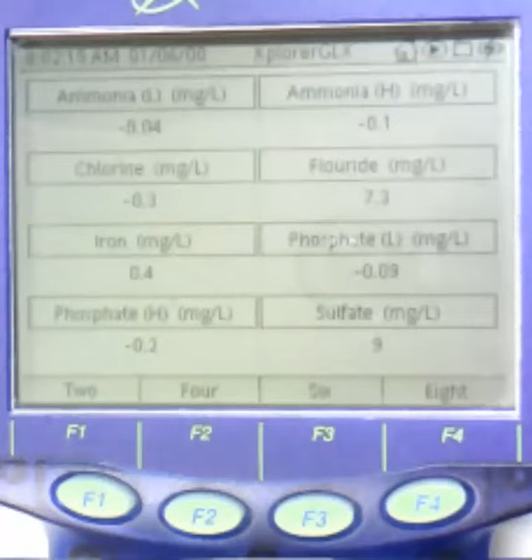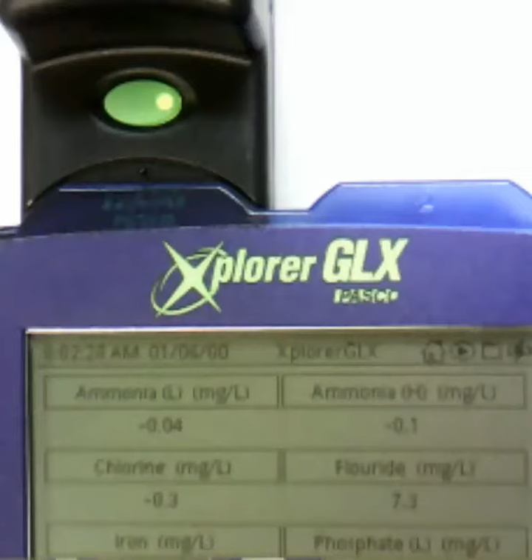So now I'm going to calibrate my colorimeter. I'm going to do that by removing the calibration ampule from its protective case, and I'm going to place it into the sensing chamber for the water quality colorimeter. Next, I'm going to place the light cover on top of it, so the only light passing through the sample is what is produced by the colorimeter. Next, I'm going to press the calibration button, and I'm going to wait for the green light to turn out to let me know that the device has been calibrated.